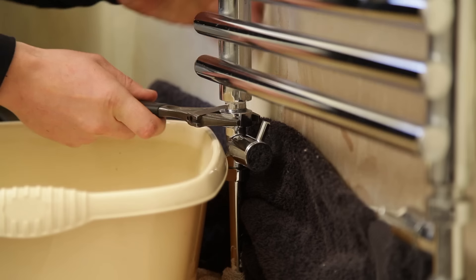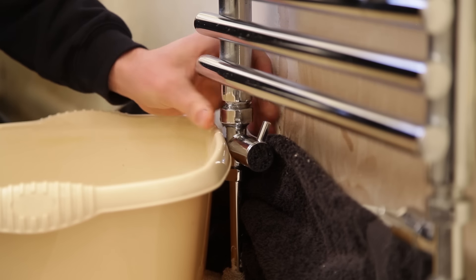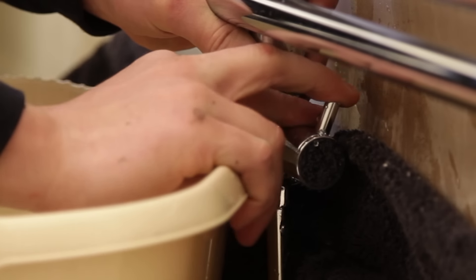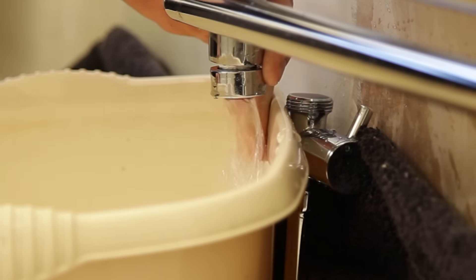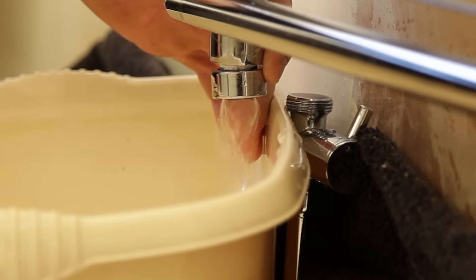Using your adjustable spanner undo the valve nut and then pull the open outlet over the tail. Once the water has stopped, open the bleed valve using your radiator key. This is to rid of any remaining water left in the radiator.